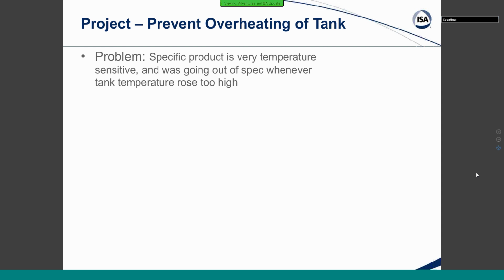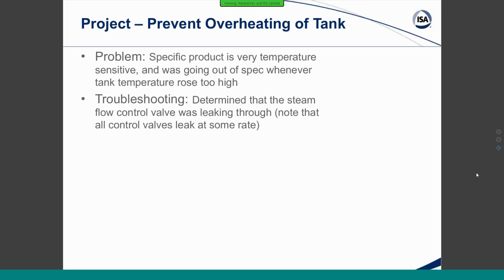Okay. In this case, we were having poor control issues on one of our tanks out in the tank farm. The product that we were storing in this tank is very temperature sensitive, and whenever the tank temperatures got too high, the product would go out of spec and have to be reworked. So we did some troubleshooting, pulled maintenance in on this one, and determined that our steam flow control valve is leaking through. It's important to note that all control valves do leak through. There's some rate set by the manufacturer that they leak through at. In this case, we had more than we really wanted.